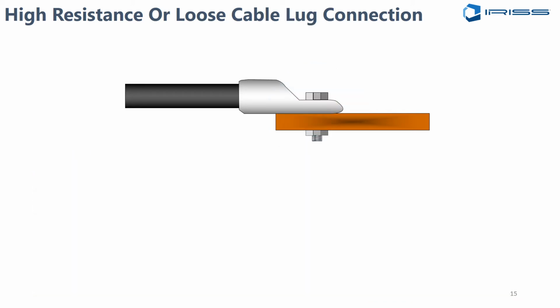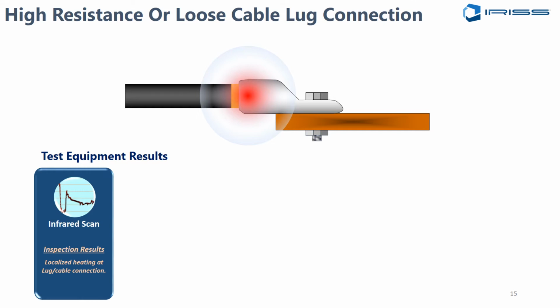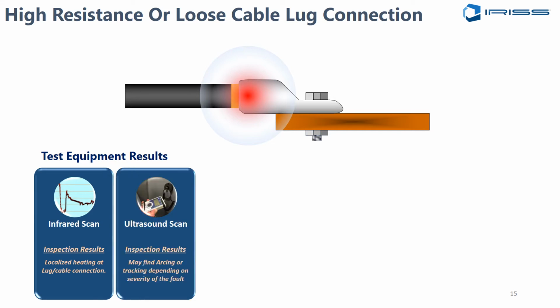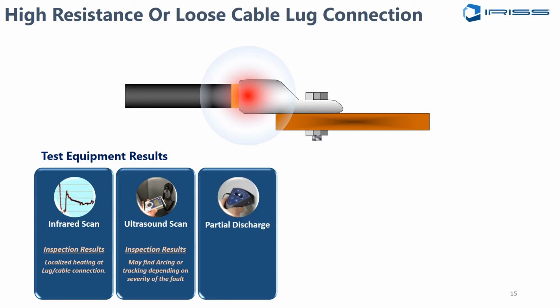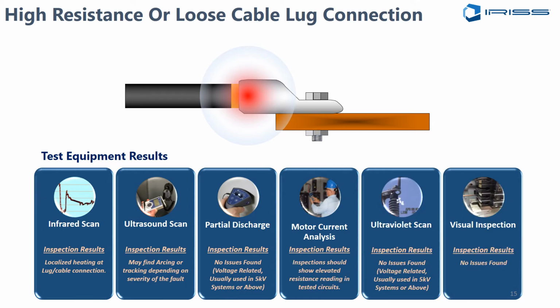Now, another area where we have some similarities is obviously a loose cable lug. That is going to give me identical results to a loose or high resistance connection, but the actual high resistance is now in the lug and not in the bolted connection. So I'm going to get all the same results. What we say here, typically as an electrical engineering firm, is that we would advise, if you find an overheated connection, that you would actually cut the lug off.